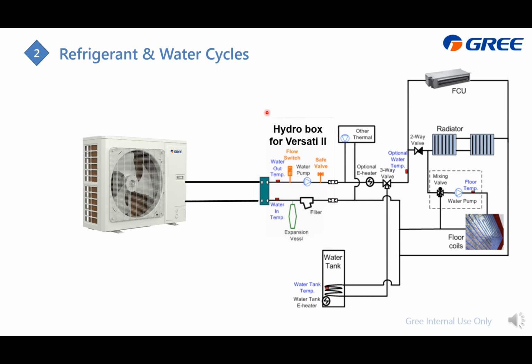And also for this part, it is the VERSATI2 hydro box. And then you need to install it for the water cycle. It is from here, and here is how the water flows. Water comes in from here, and after heating up, for example in heating mode, we can send the hot water to the water tank from this three-way valve. If we choose to heat up the FCU or floor coils, just change this direction, it's okay, just like this.